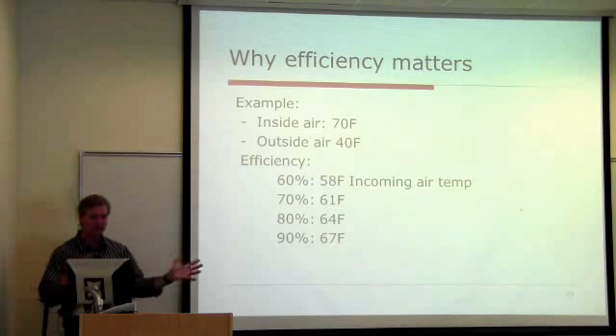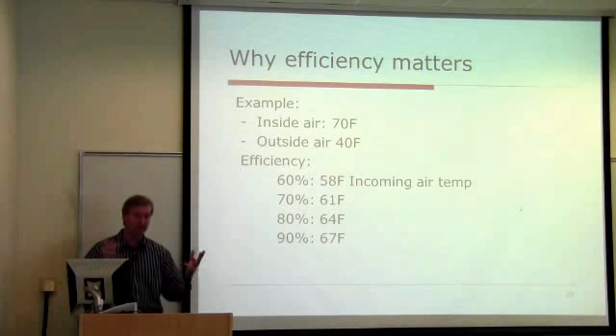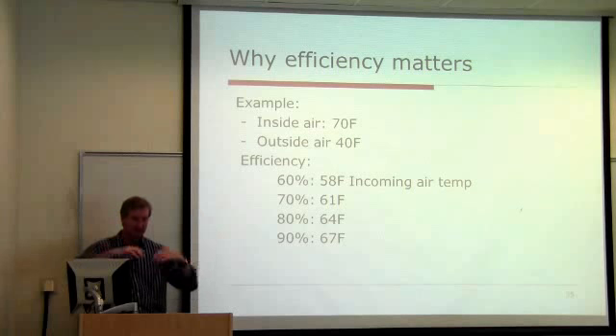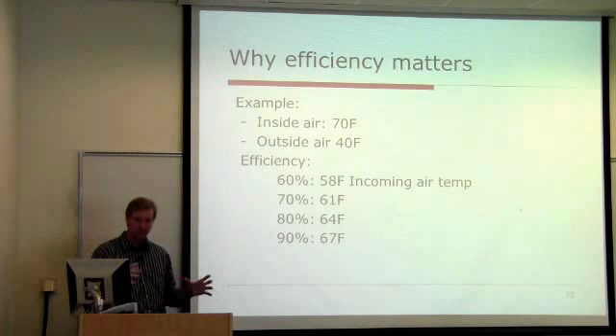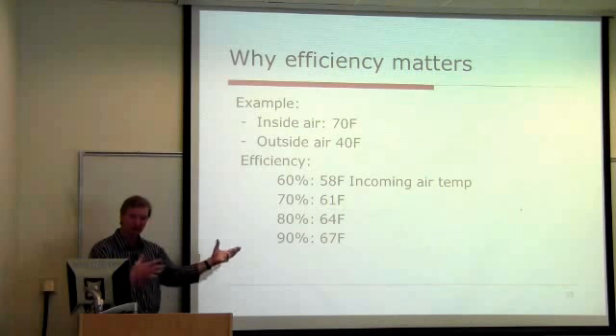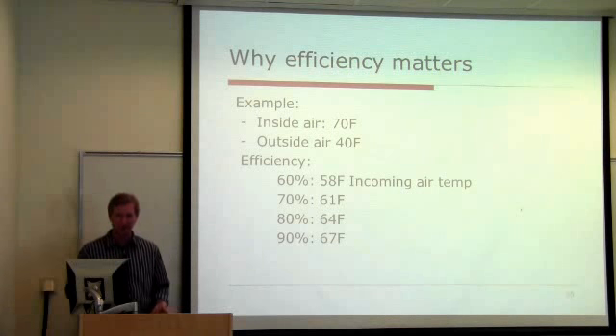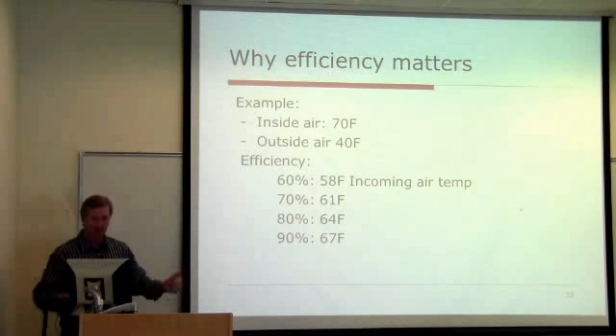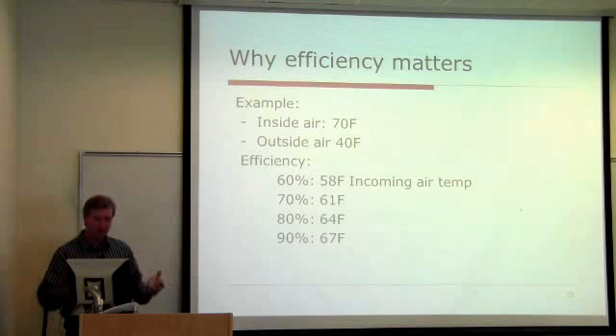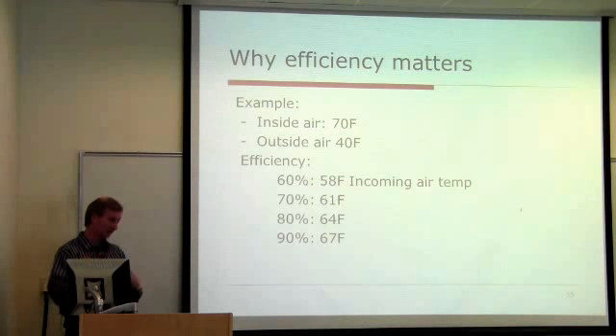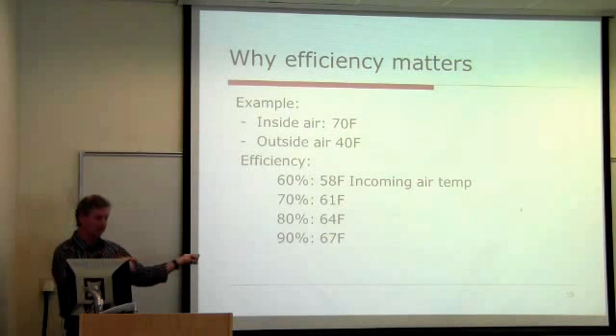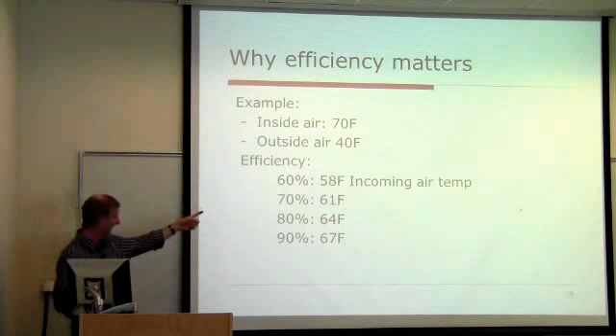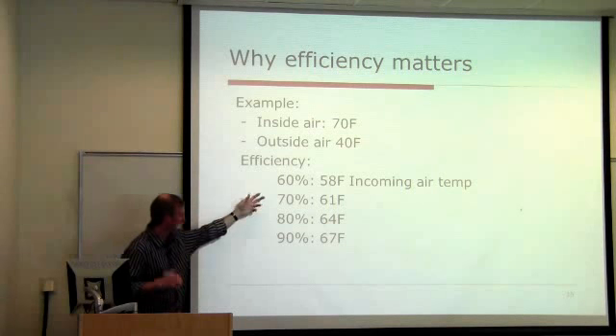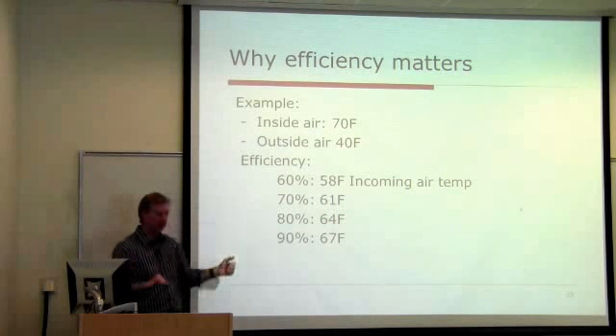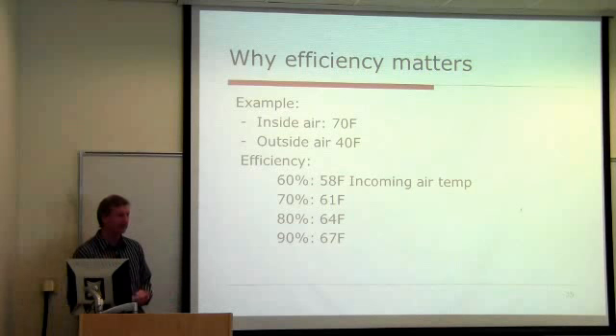So that big 1,000, 1,500 CFM fan's running, which is taking a lot of energy. That's the only time it distributes fresh air to the entire house. So in your shoulder seasons and in the summer here, you're not running your HVAC system. So we usually put in an independent fresh air system. But you kind of have to take a look at that. A lot of HRVs are connected directly to your forced air system, and they're using less expensive units that have this efficiency. But since, like I said, you're not feeling the air.